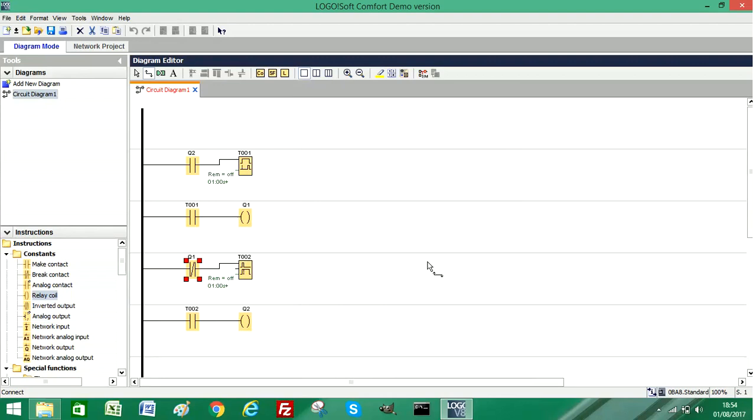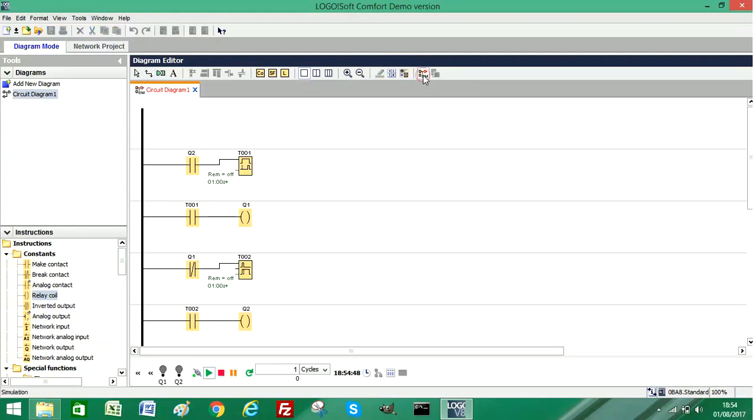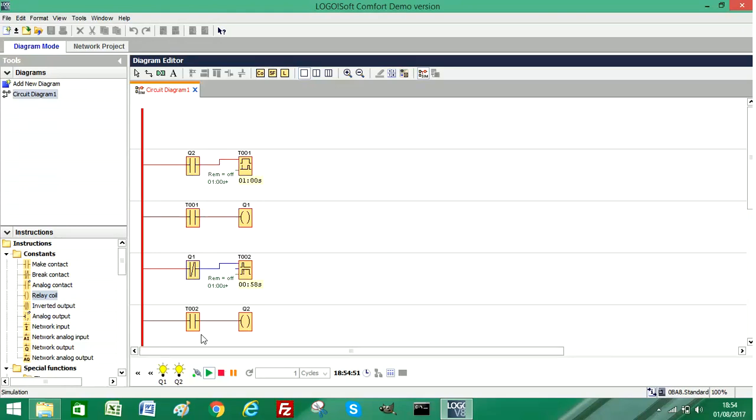Now what this will do is create a one second pulse on output Q1, and we'll be able to simulate this if we start our simulator now. From the menu I'm going to select simulator, and as you can see near the bottom, our Q1 output is flashing at approximately once every second.